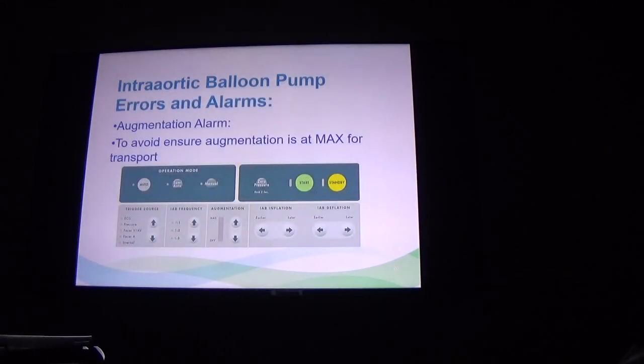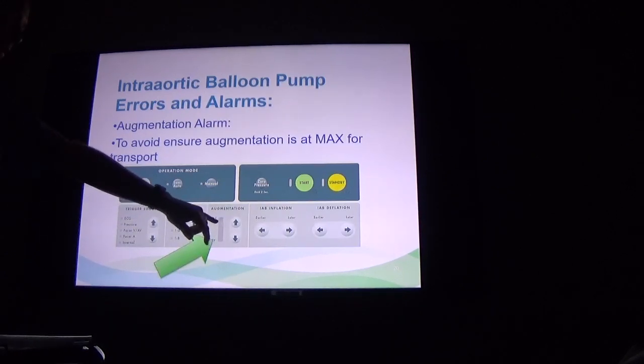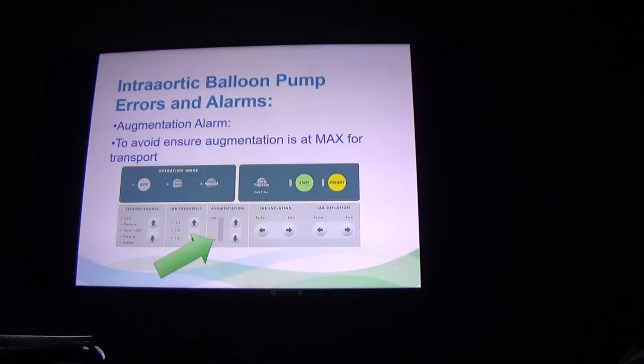The other thing you may see is an augmentation alarm, especially if people are weaning on the devices. And to avoid this, we're going to take augmentation all the way to max, or 100%. You just crank it up all the way. That will avoid most of the augmentation alarms just by doing that.